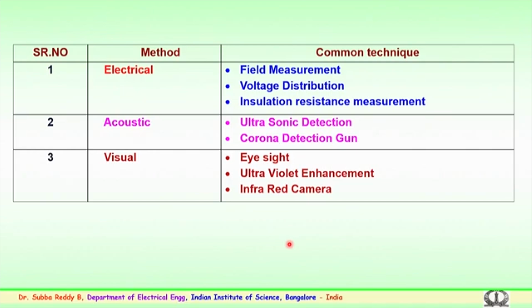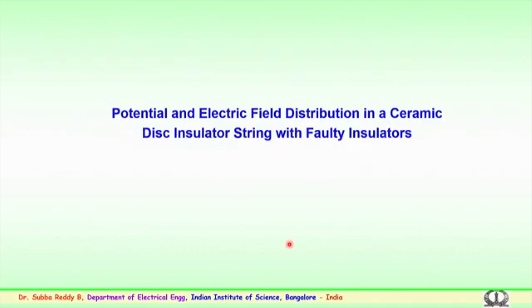We have also tried to understand the phenomena, how it happens, how the field gets modified in case of a faulty disc in a string. The modification of potential and electric field, particularly in case of ceramic disc insulators with faulty units in a string, is studied for various voltage levels, both experimentally and theoretically. It gives important information to the utilities, particularly on whether the change is necessary immediately, and where exactly the faulty disc insulators, in case available in the string, are to be replaced.